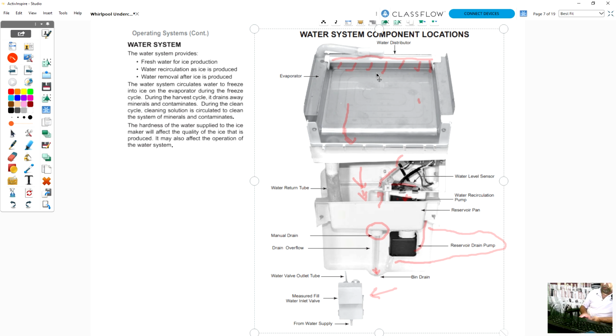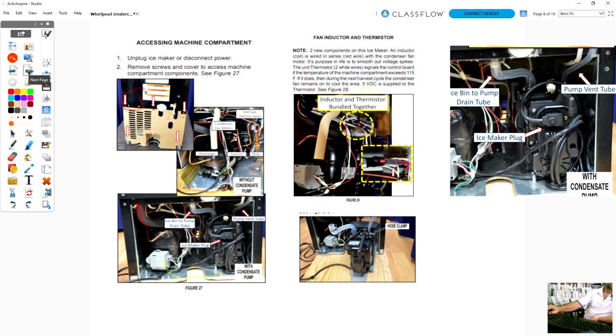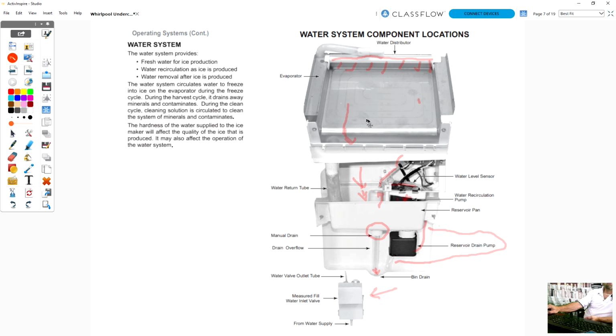Once it starts flowing over, the ice starts building up on the evaporator and starts to get thicker and thicker, and we're going to start running out of water in our reservoir as it turns to ice up here, and that's when our water level sensor says, hey, the ice should be thick enough, let's go ahead and drop that ice. At that point, we initiate the harvest cycle. Now what happens in the harvest cycle is we energize the hot gas valve, which is back here, compressor continuing to run, and that runs hot refrigerant over the evaporator and pumps that high pressure refrigerant here so the slab of ice will just slide off.